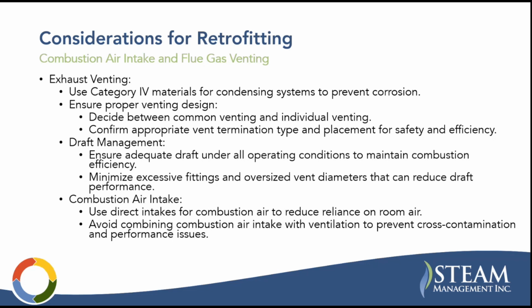Draft management, you want to ensure adequate draft under all operating conditions. You want to minimize excessive fittings and oversized vent diameters that can reduce draft performance. So this is particularly important if you think about just lining your existing stack for the condensing boiler flue gas outlet. That can be done, but you have to make sure that it's an appropriate diameter. So you can't just line the stack and be done with it. You got to evaluate that, and also it might have too much height and give you too much draft, and then you need to have a draft controller.